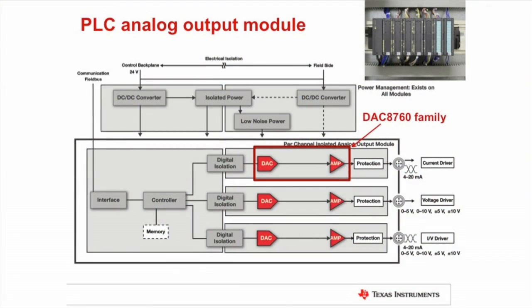Here is a block diagram for a PLC analog output module. The backplane on the left interfaces to the field instruments on the right through this PLC analog output module. There is an interface component going through a digital controller, through a layer of isolation, which then talks to the digital-to-analog converter. The predominant component on this module is the DAC, which sets the performance. The DAC typically interfaces with the amplifier, and together they interface to the field equipment with either a current output or a voltage output.